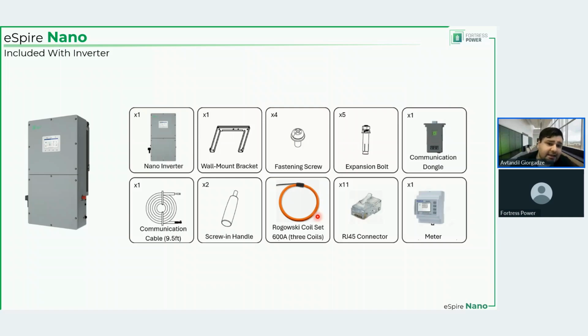In that case, you will obviously need bigger Rogowski coils, and you can request them from us. Based on that request, for an additional price, we'll provide bigger Rogowski coils. And you cannot use some random coils, because this inverter is certified with the meter that is shown right here and with the Rogowski coil set.